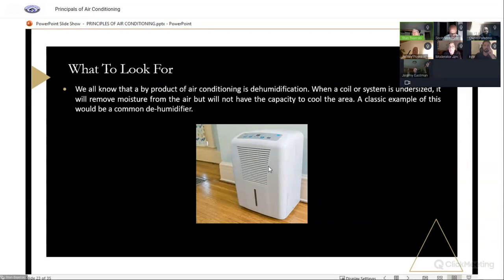So if you were in a house, and I think I got a slide about this, but we'll talk about it now, and it's a moderate day. It's not like 100 degrees outside. And that system, the entire time that you're in the house, doesn't cycle. There's probably something wrong. Could be undersized. There could be other things wrong. It should be achieving its temperature and shutting off at some point, especially the cooler the outdoor temperature, unless there's some other kind of heat load in the house.